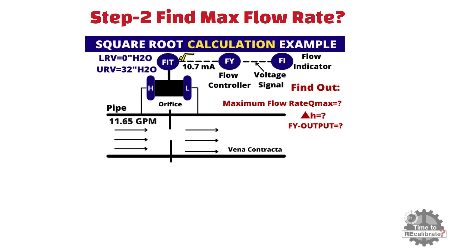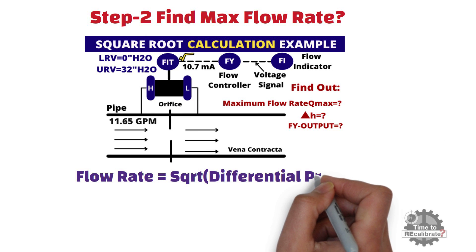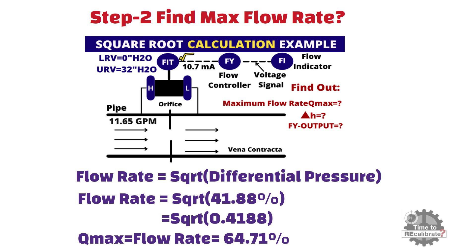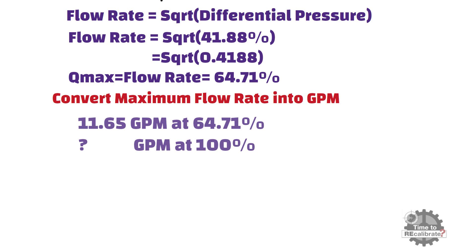Step number 2: Find maximum flow rate. As we know, flow rate is directly proportional to the square root of differential pressure. Put 41.88% into this equation and take the square root of this value — you will get 64.71%. This is the maximum flow rate in percentage. Now convert this maximum flow rate into GPM. When you put the values into the equation, you will get 18 GPM as the maximum flow value.